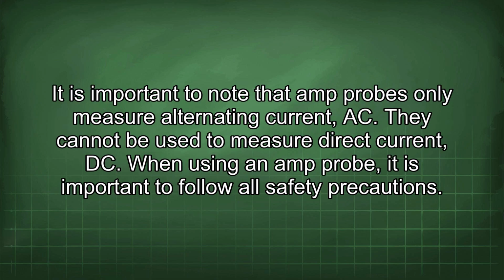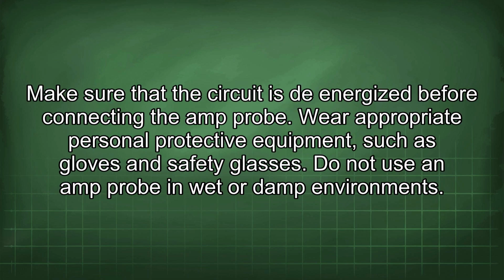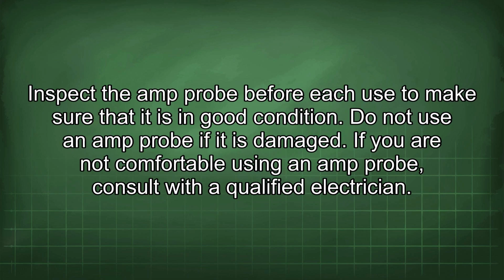It is important to note that amp probes only measure alternating current, AC. They cannot be used to measure direct current, DC. When using an amp probe, it is important to follow all safety precautions. Make sure that the circuit is de-energized before connecting the amp probe. Wear appropriate personal protective equipment, such as gloves and safety glasses. Do not use an amp probe in wet or damp environments. Inspect the amp probe before each use to make sure that it is in good condition. Do not use an amp probe if it is damaged. If you are not comfortable using an amp probe, consult with a qualified electrician.